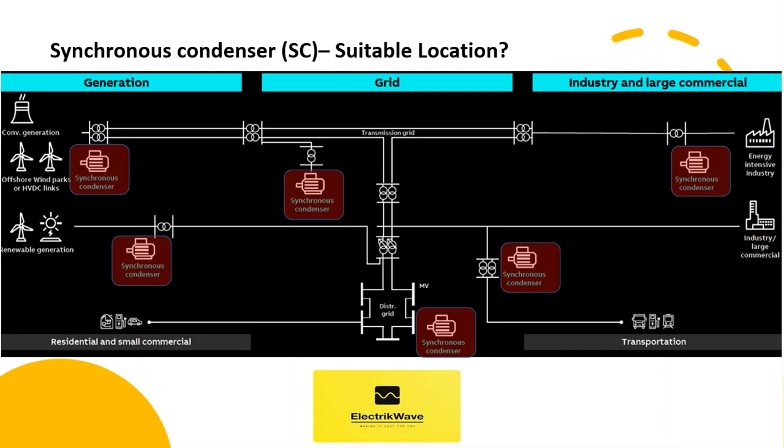They increase fault current and reduce the transfer of power quality issues, flicker, harmonics, unbalance, to the grid. Synchronous condensers can mitigate voltage stability issues associated with heavy industries like mining, especially when fossil fuel generators are phased out. Other capabilities include supplying short circuit capacity to strengthen the network and prevent voltage collapse during heavy load peak. They also increase fault current and reduce problems with motor starting and demanding loads like gearless mill drives and furnaces at mines.